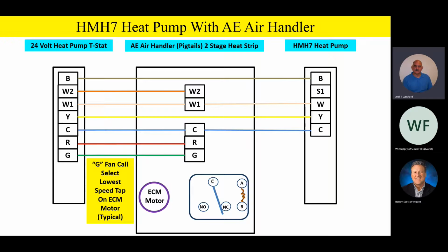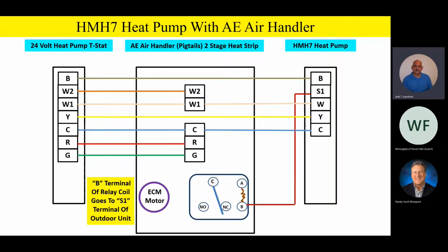So basically, you're going to have 1 through 5 speed taps. And I normally like to recommend just go G to speed tap number 1, and that'll give you a nice low airflow, running the air across the filter, and keeping the air moving in the house. Really nice and quiet. So let's talk a little bit about this relay and how we're going to engage that relay for airflow reduction. So one side of the relay coil, now remember team, this is a 24-volt coil, just a single pole double throw switching relay is all this is. You'll notice one side of that 24-volt coil on the relay goes up to S1 to the outdoor unit. The other side of the coil will go to C terminal, 24-volt common.